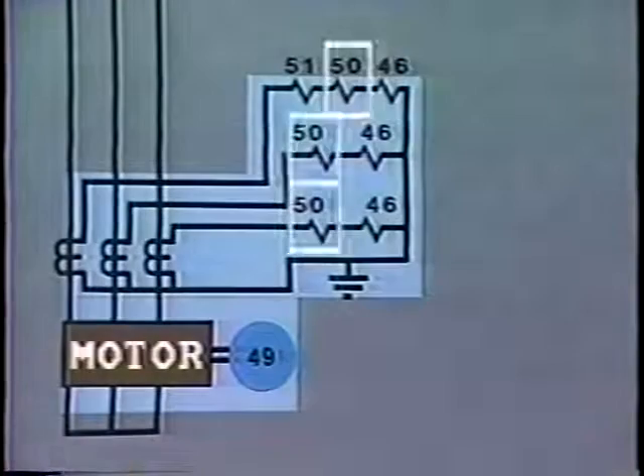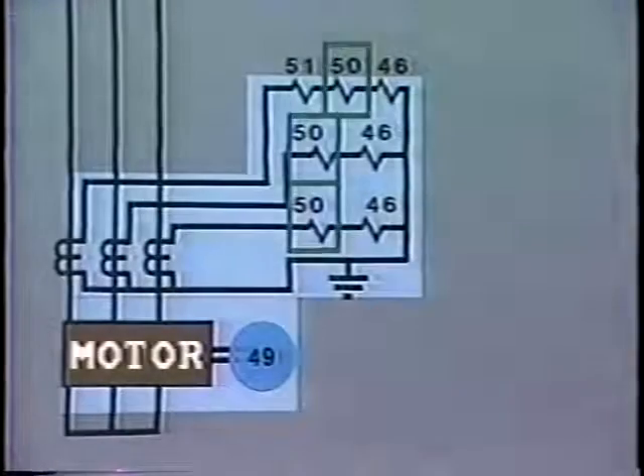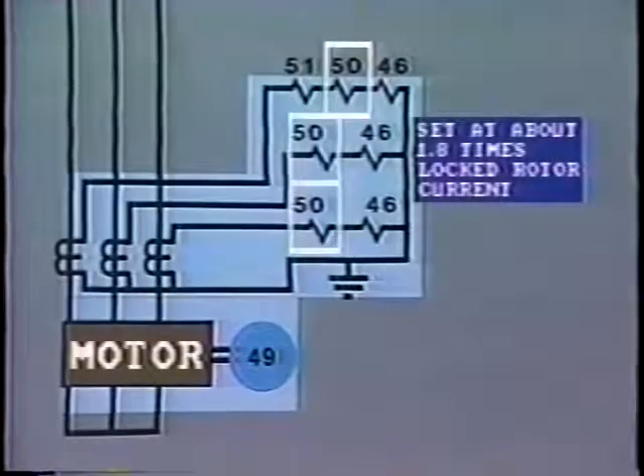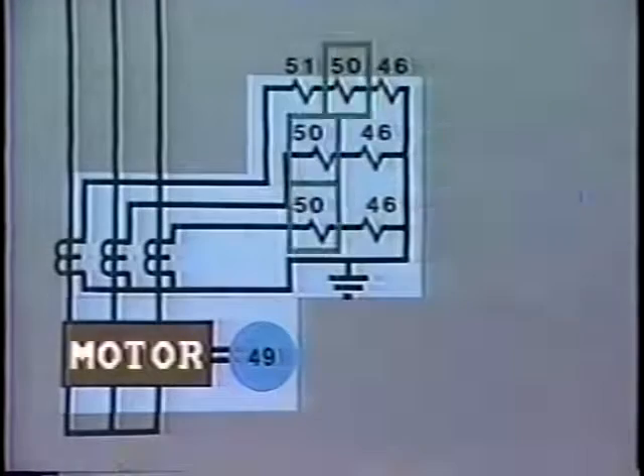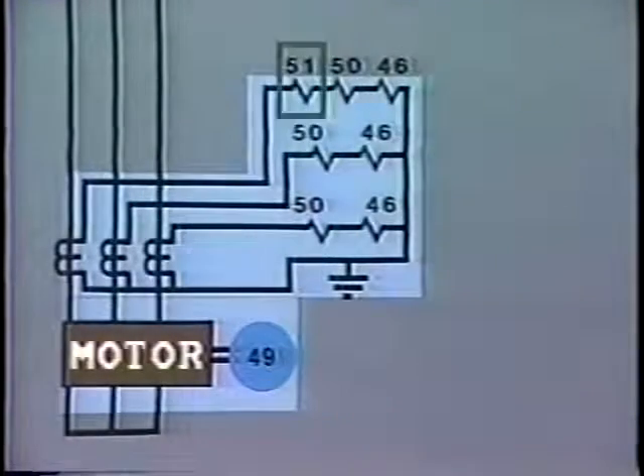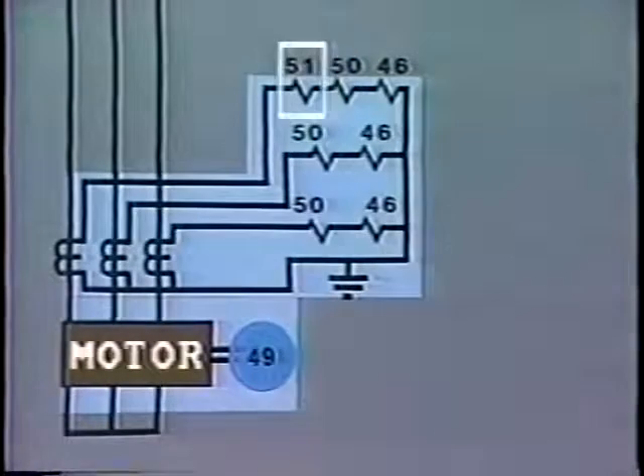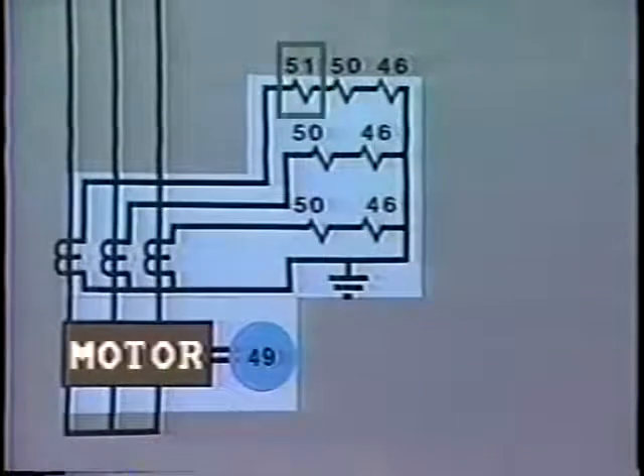In addition to this, overcurrent relays are fed from CTs in each phase of the power supply to the motor. These instantaneous overcurrent relays, 50, are installed one per phase to protect against very high-level stator faults. This relay is usually set at about 1.8 times locked rotor current. Relay 51 here is a time overcurrent relay set to protect the motor against overheating due to overload. This relay should also protect against locked rotor conditions.